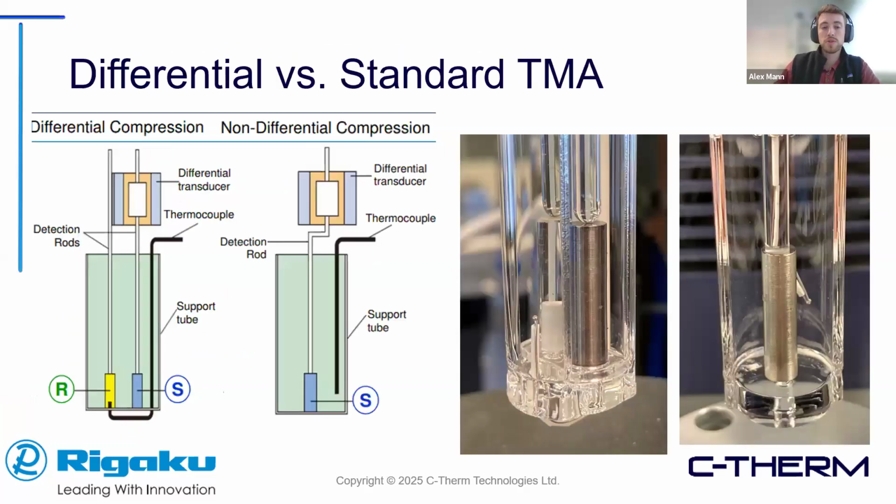So this is what the differential and standard setups look like. We can see here in the standard, we just have one rod. And then in the differential, we have two rods, one rests on the sample, which is right beside the reference, which has its own rod.